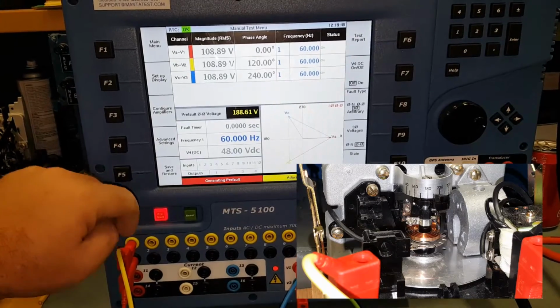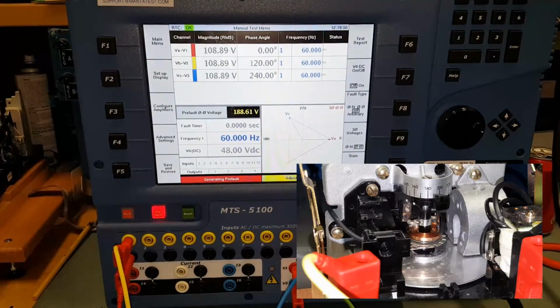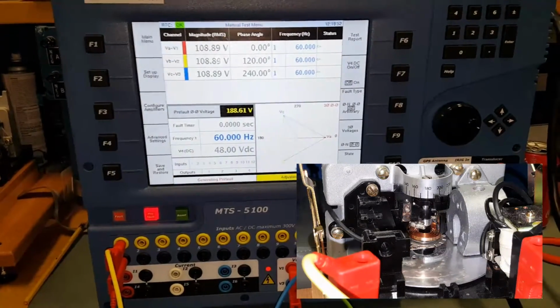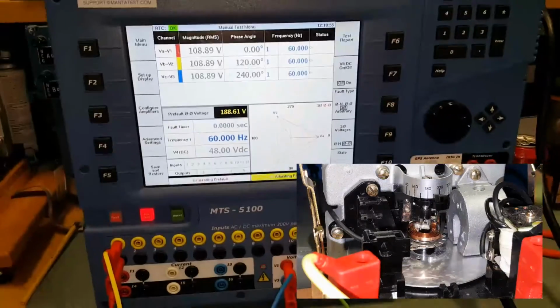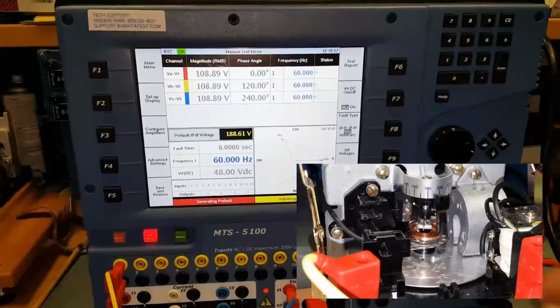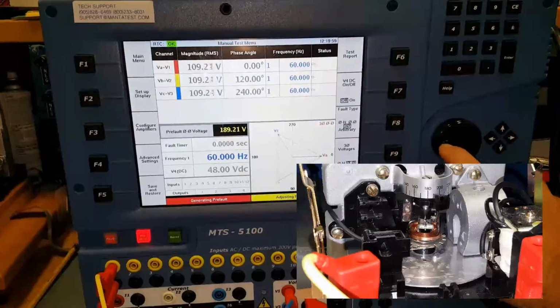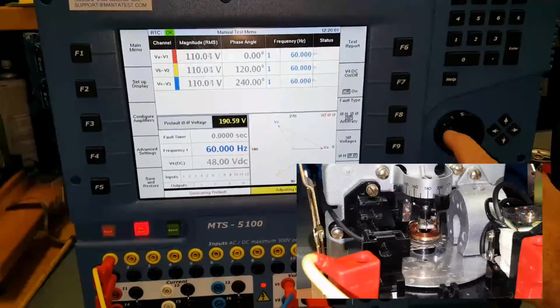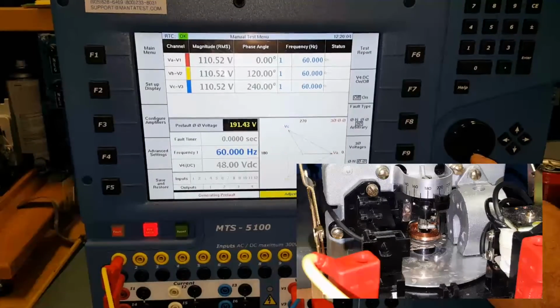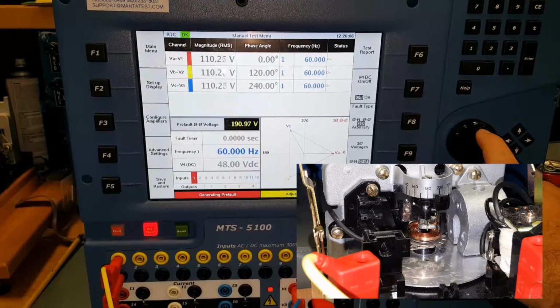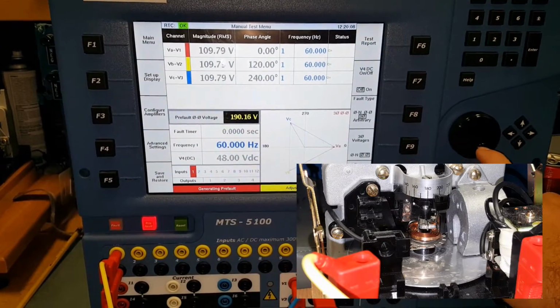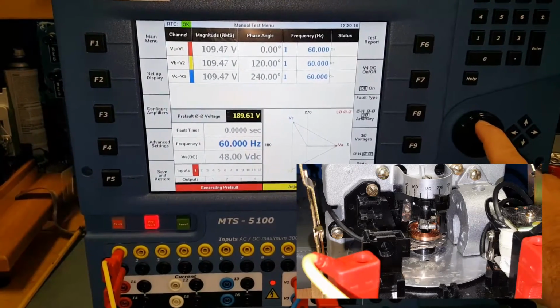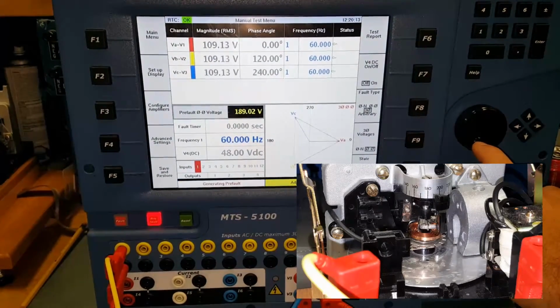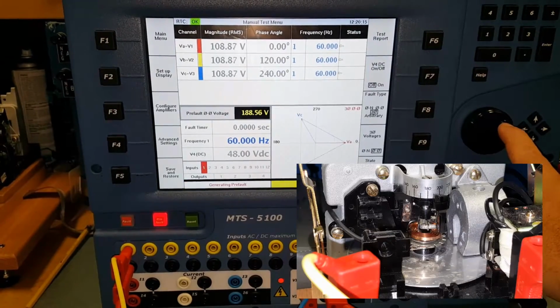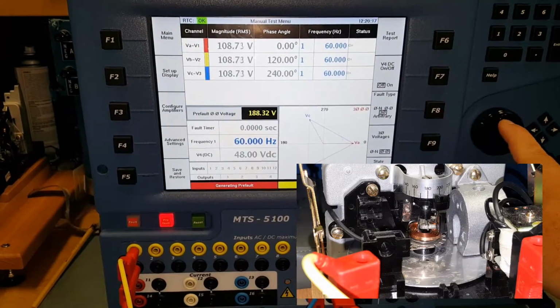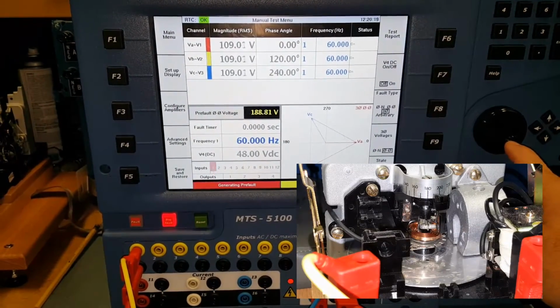For the overvoltage pickup test, we're going to want to find out our nominal voltage that's given on the setting sheet, calculate the acceptable range, which in our case is going to be plus or minus 3%, and then we're going to ramp up the voltage until the high voltage contact is made up, and we can see that on the screen there with the Manta for the inputs. Once that's made up, we can back off a little bit, ramp it back up, find out where the pickup point is, and record accordingly.